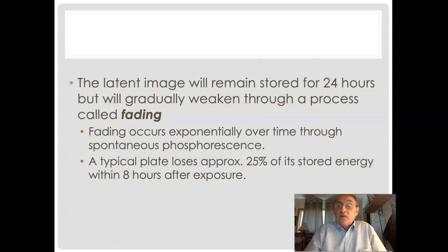Important to remember with CR plates that the latent image will remain stored for about 24 hours, but will gradually weaken through a process called fading. And fading occurs exponentially over time through spontaneous phosphorescence. Essentially, we start to lose the intensity of the signal.